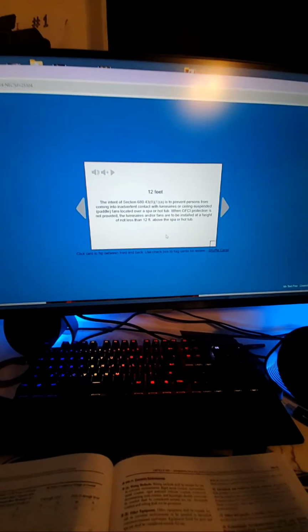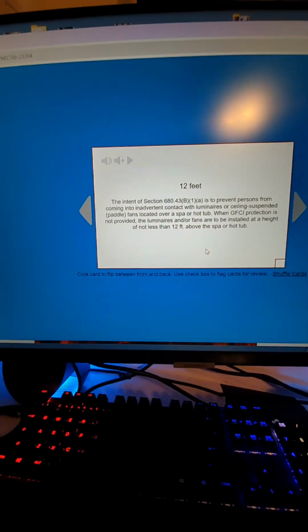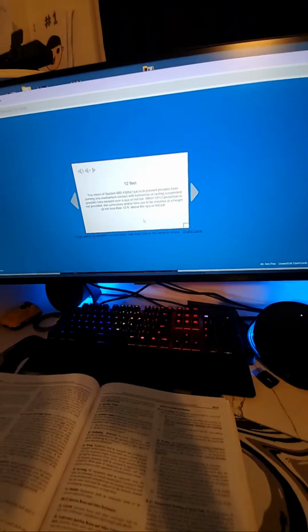We're going to go with 5 feet because the code book says it. But I don't think it's 5 feet. But it says 5 feet in here. We're just going to go for it. 5 feet. It's 12 feet, what I said before you even started this. 680.43(B). Where is it? 680.43(B). See, I psyched myself out. Because that's what I would call if I was in the field and I saw something. You know, we always call 12 feet.